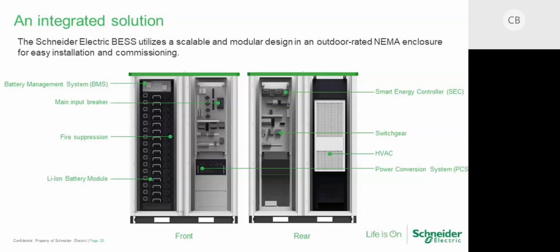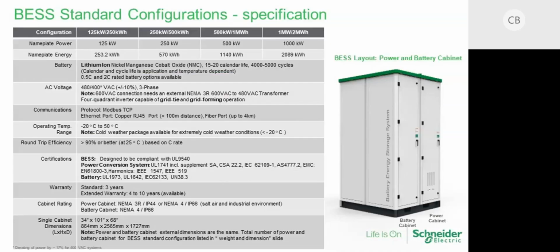What you see here on this slide is basically the rear view on the right and the front view on the left. So these are the two cabinets. One is the electronics, and then multiple cabinets with the inverter, and then multiple cabinets of battery, depending on how big a system we want. In our offer, we have 4 standard offers we provide, and we have a 125 kW. So the first line here is the amount of power the system is able to support at any given point in time. And then the nameplate energy, these are the kilowatt hours, right? In the 125 kW system, we can provide 125 kilowatts for the duration of 2 hours. So therefore, the total energy stored in there is 250 kilowatt hours.